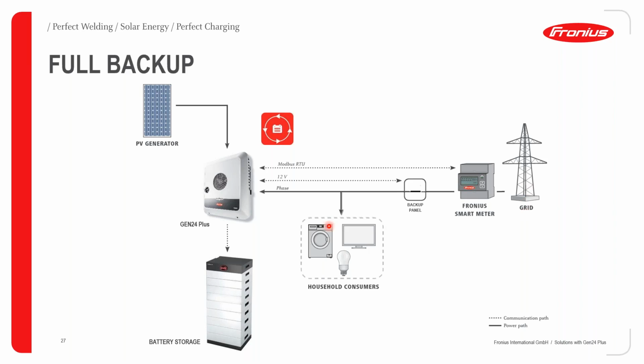What do we do? We need to install a backup panel - this is the only additional component needed for full backup, on top of your batteries. This backup panel is controlled with 12-volt signals from the Gen24 Plus. It's basically a bunch of NC and NO contacts alongside a Fronius smart meter, which is also very important and communicates with Modbus RTU to the Gen24 Plus.